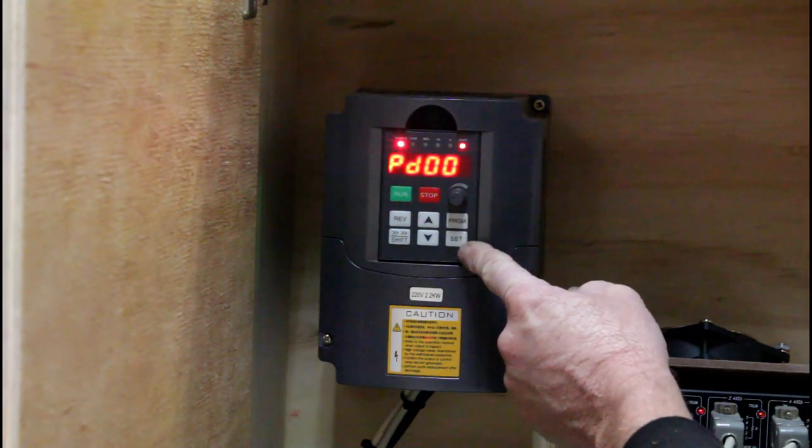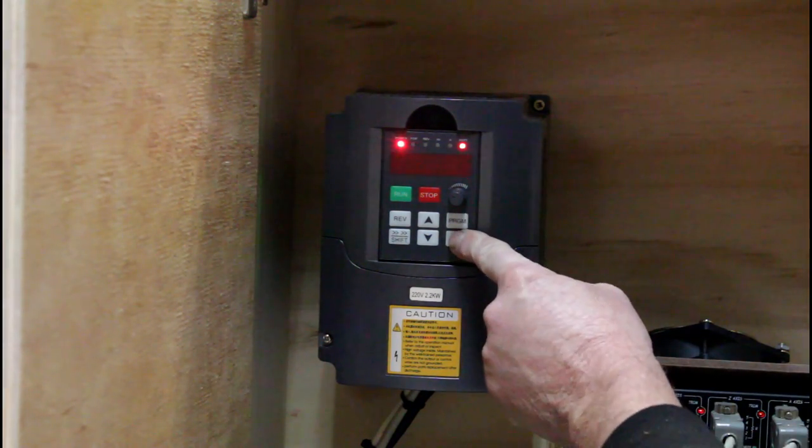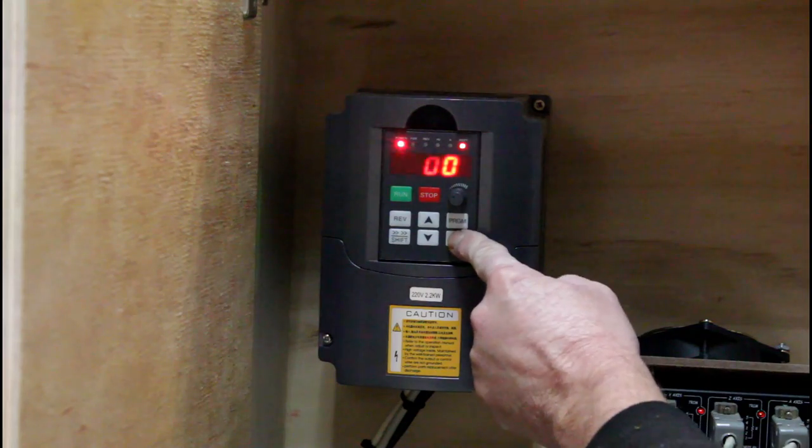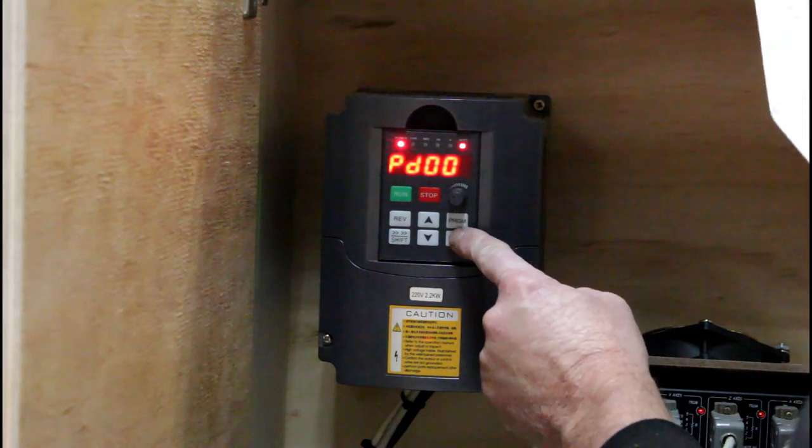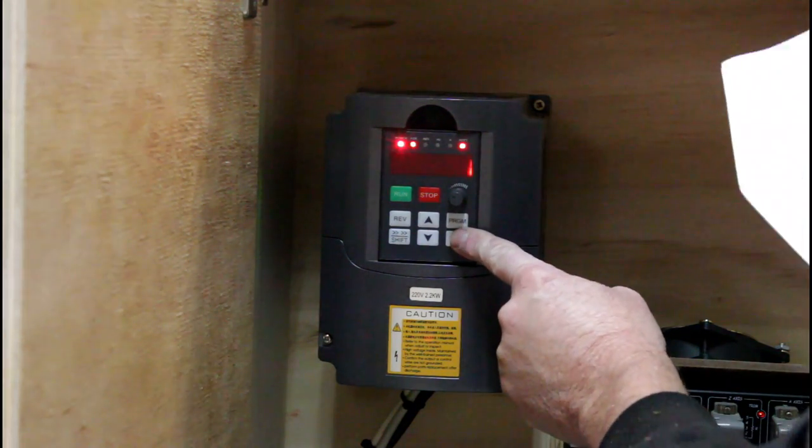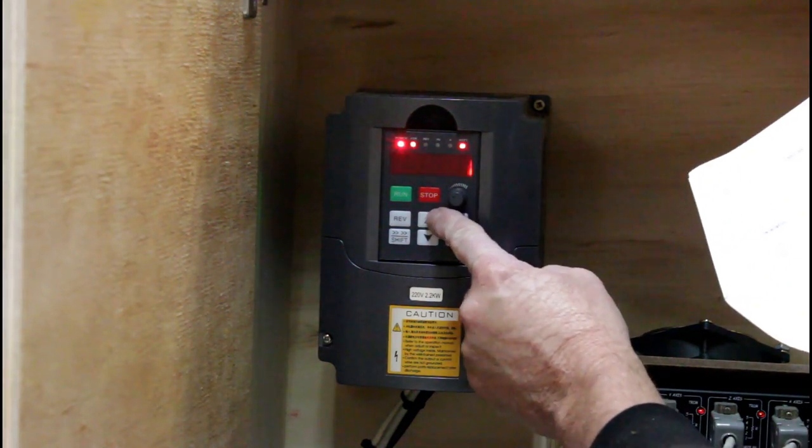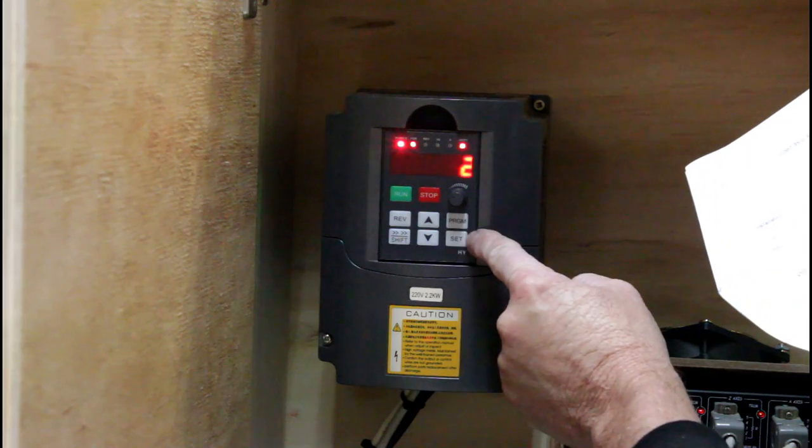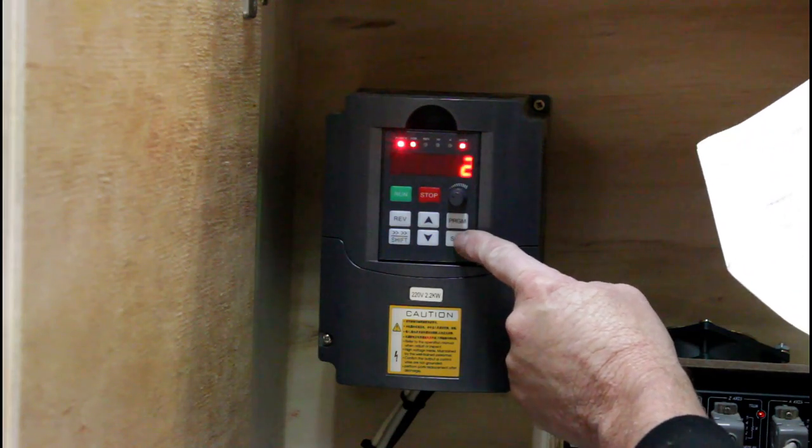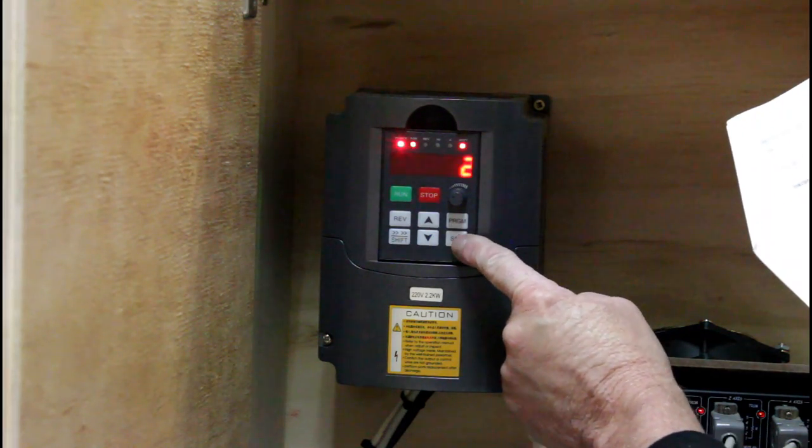I need to check the VFD is correctly configured. First register 0 needs to be set to 0 to enable changes. Registers 1 and 2 need to be set to a value of 2.